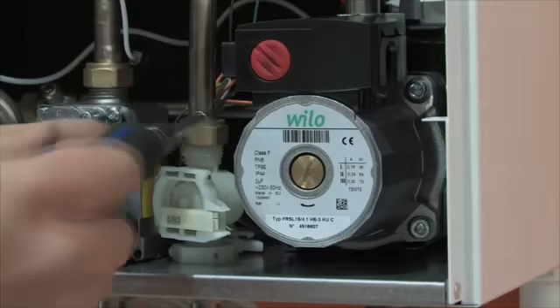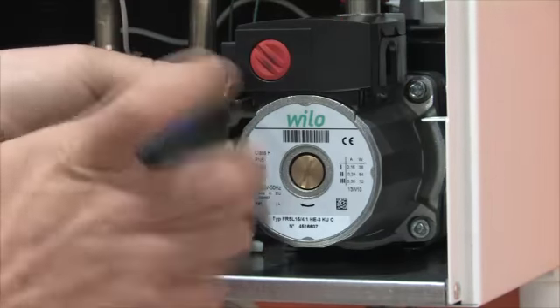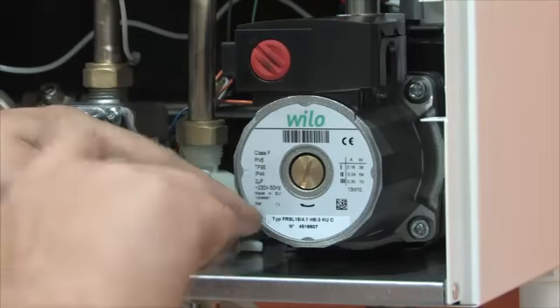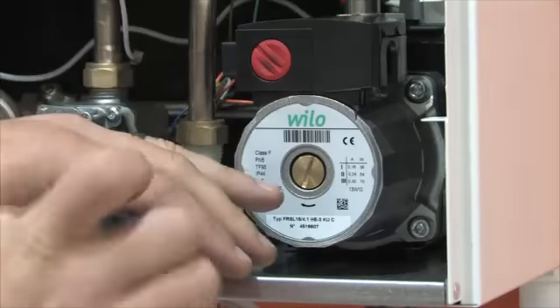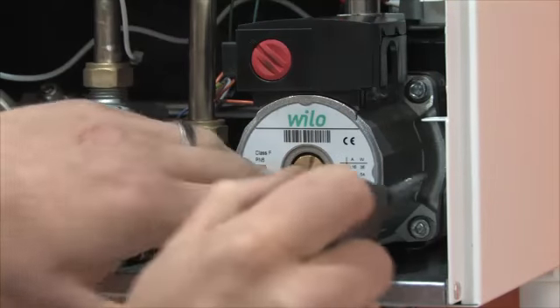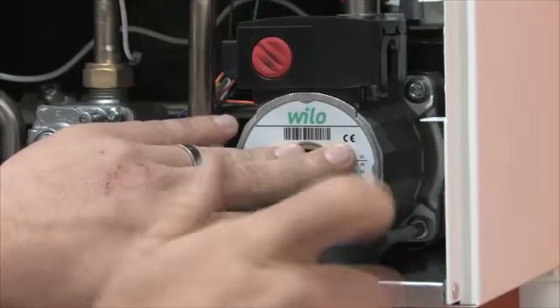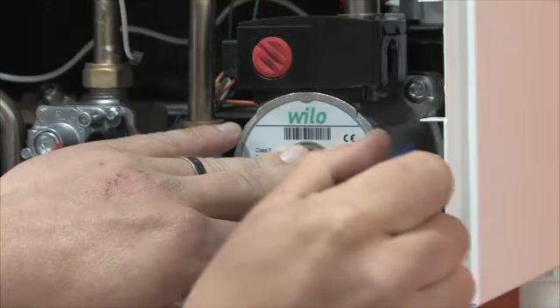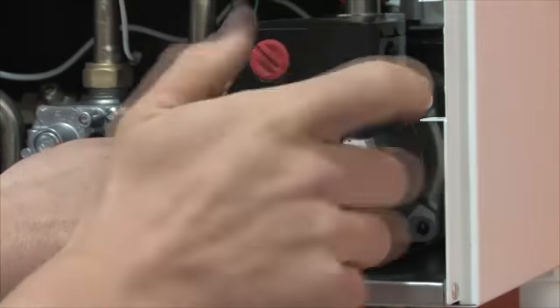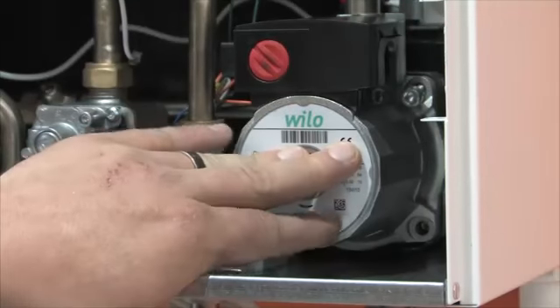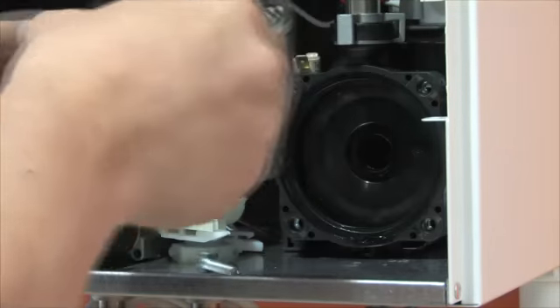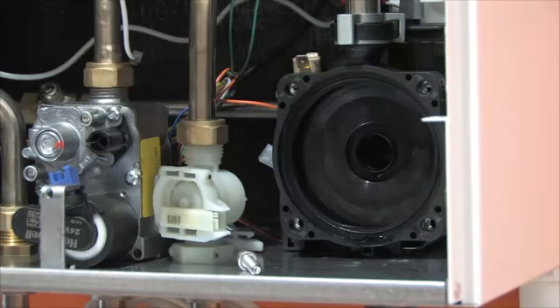The Modena HE uses a standard Wilo pump, so it is straightforward to replace if necessary, and it already complies with the new modulating regulations which come into effect in 2015. An added advantage is that the pump is controlled by the PCB as opposed to being a modulating pump, which is costly to maintain, so this is another money-saving feature. Pump head pressure is 4 meters and 6 meters respectively for the 27 and 32C models.